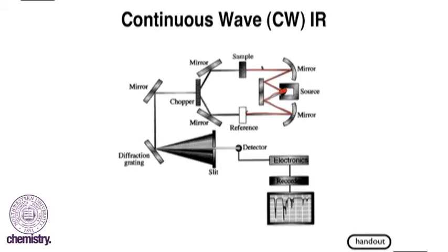If we take those two beams and recombine them, then we will be subtracting out any gases like carbon dioxide, any gases that might be in the room that could interfere with our sample. Then we take that combined IR signal and pass it through what's known as a diffraction grating.